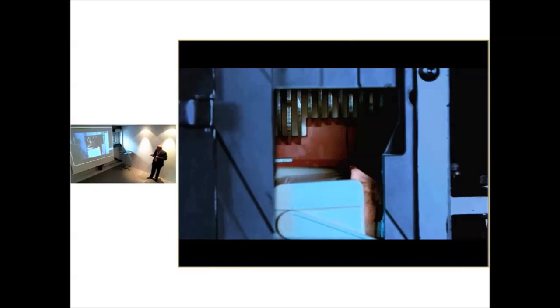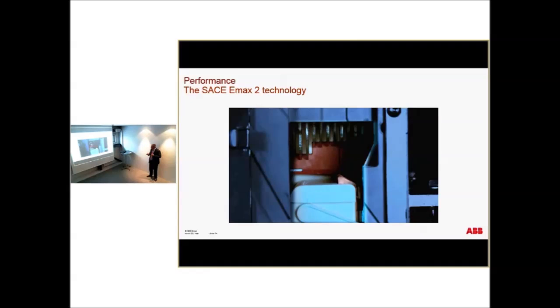Now you see the contact, how it works now. The point now, this is very well insulated. The movement of the contacts is more horizontal than vertical now. Important point is to have arcing contact here, main contacts here. So when the breaker opens, it's important that the opening is done by this contact, and it has to stay. It has to stay. The current needs to be maintained by the main contacts. So not all ACBs have the 2 contacts. Another important point.